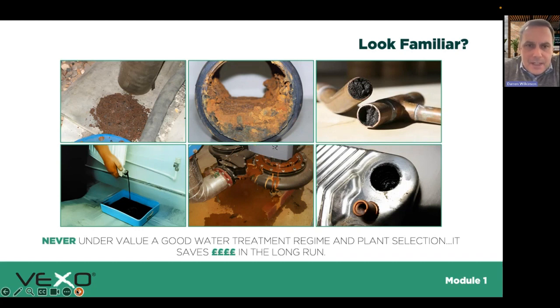In the top left is a system that has had good flushing bypasses - fan coils are all bypassed - and the contractor got those velocities to BSRIA standards around the system, removing all of that corrosion debris and pulling it out of the strainer, as you can see there. So that much heavier detritus was managed to be moved out of the system. If we don't have the right design, we're not going to remove that - and then what does that mean?